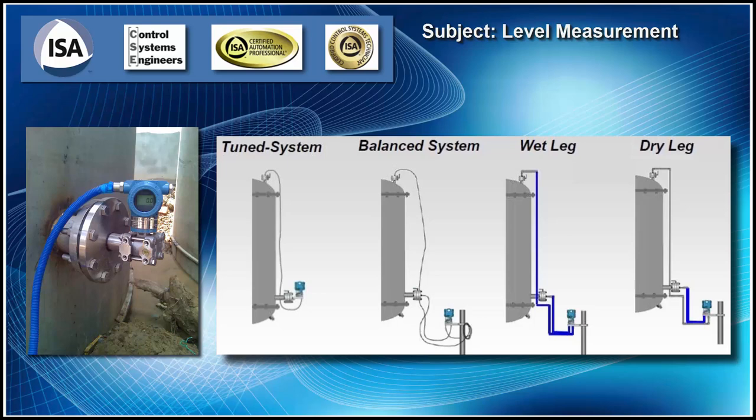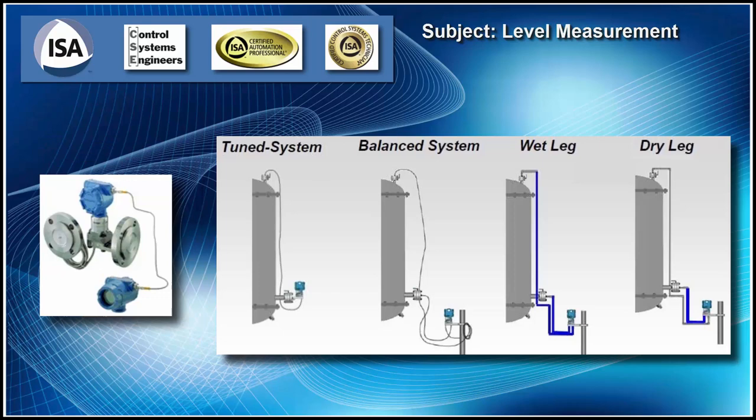What you're seeing on the left here is a Rosemount LT transmitter, and this is a coplanar transmitter. There are two diaphragms on the bottom, and one is connected to the diaphragm that bolts up to the tank at the bottom. That is the high side of the transmitter. And the capillary tube diaphragm goes to the top of the tank. What's unique about this is you can get your remote head and plug into this. Since your transmitter is bolted to the flange at the bottom of the tank, you don't want to lean down and look at that all the time. So you put your post out there and put the remote head up so that the process operator, technician or engineer can walk up and actually see what the level is.